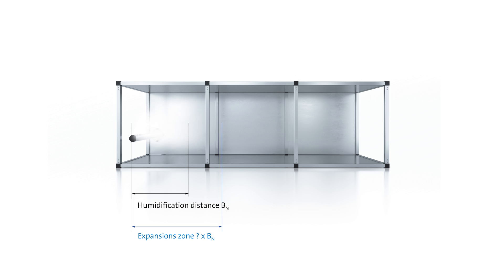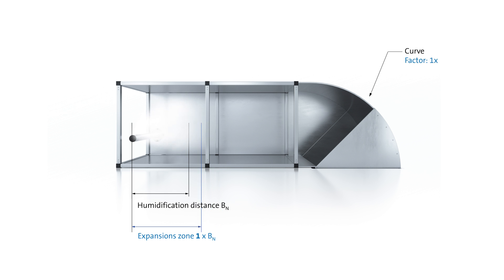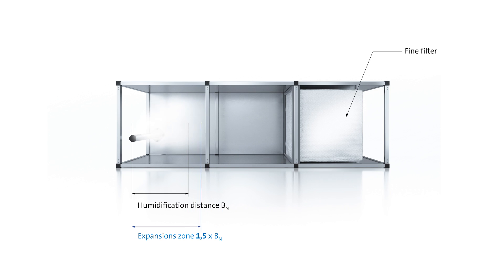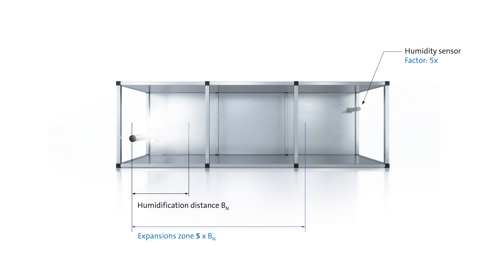the expansion zone is determined based on this humidification distance BN with due consideration of the kind of obstruction used at the end of the humidification distance. If there is an elbow, the simple distance BN is used. If there is a fine mesh filter, one and a half times the BN is used. If a humidity sensor is installed, provision should be made for five times the BN.